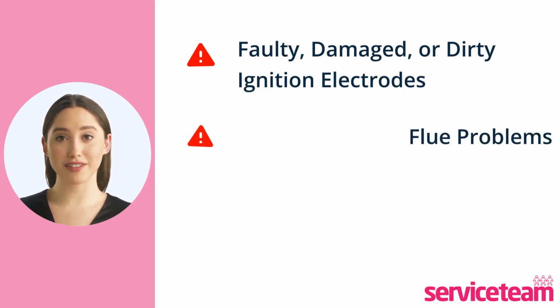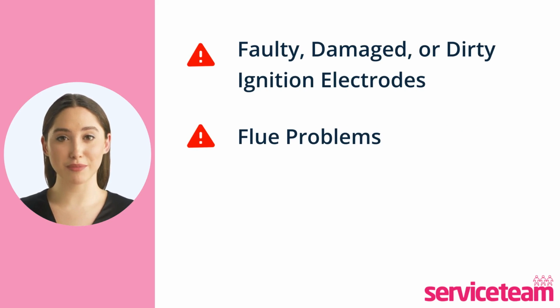The second cause of the F7 error is flue problems in the boiler. Blockages in the flue system or a bad installation can mess with how the flue system works, making the boiler think there's a flame when there's actually not. So, it's essential to keep that flue system clear and working right.